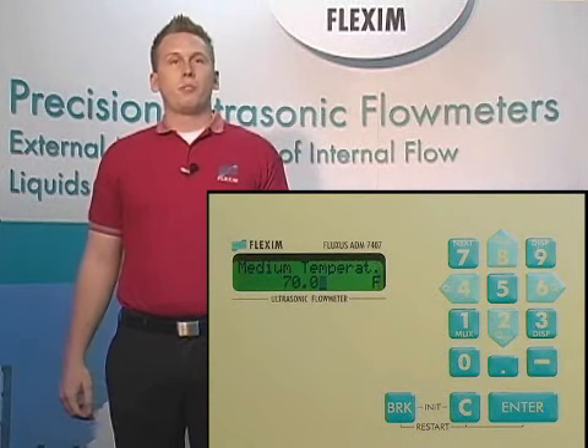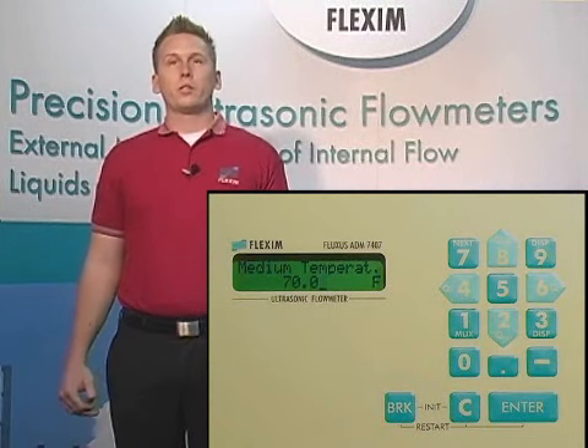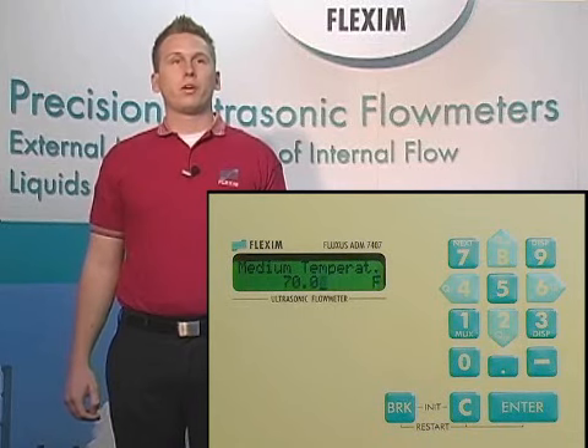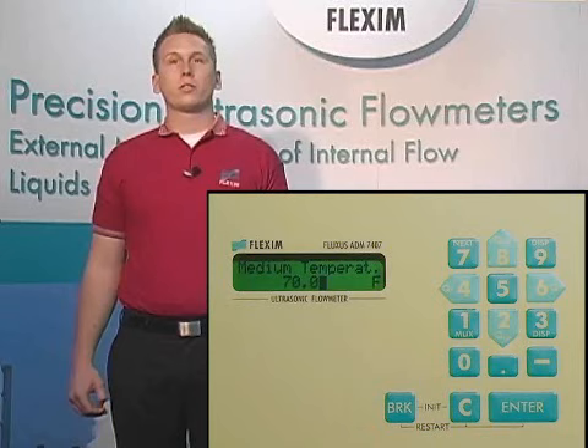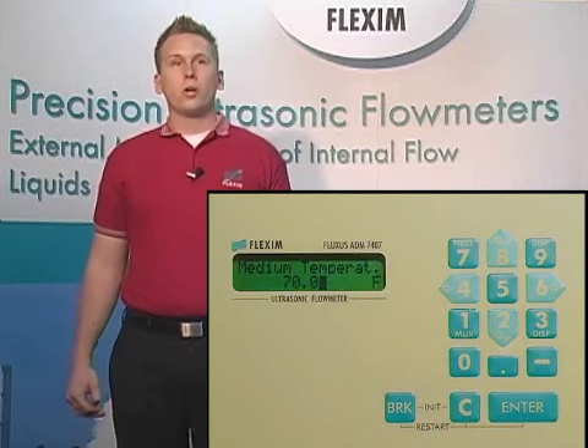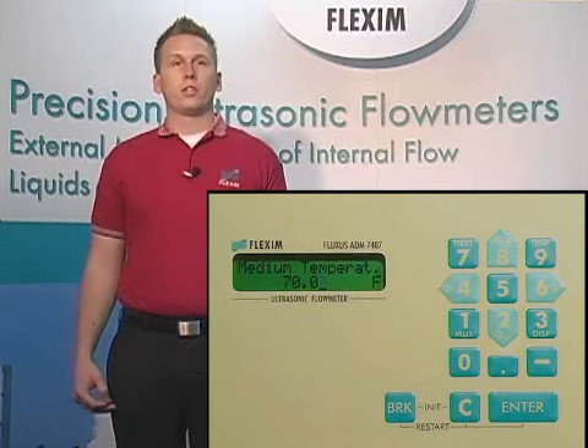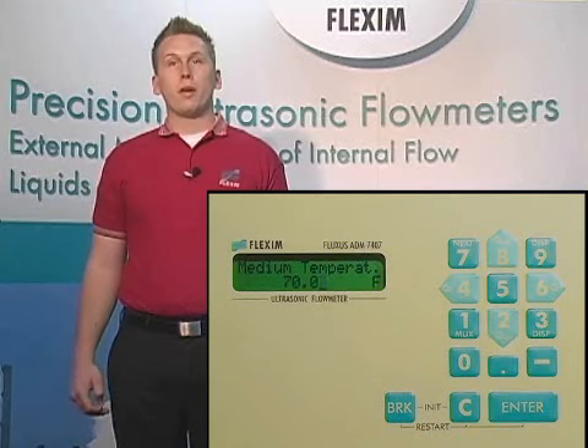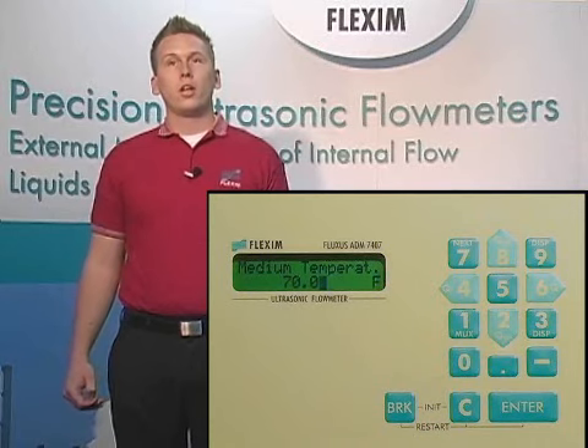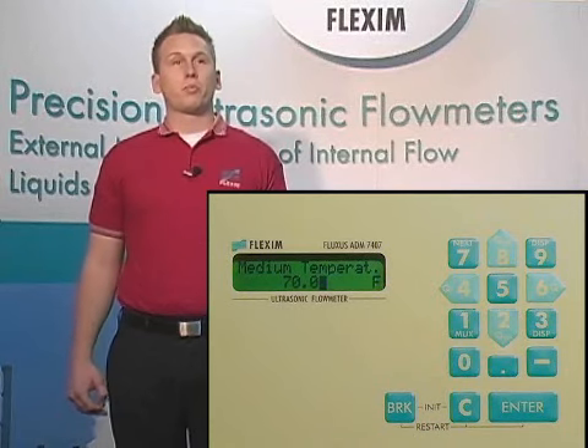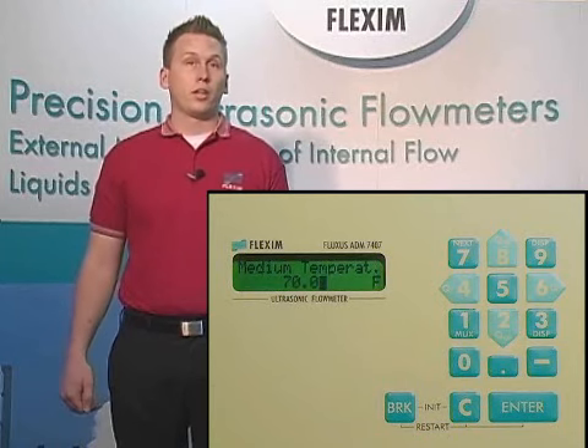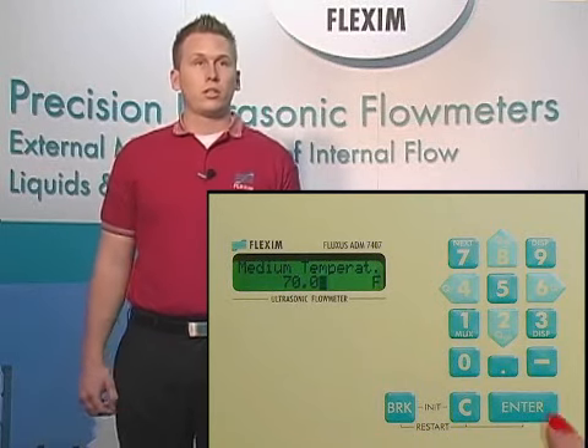Now we're prompted to enter the medium temperature. Here we need to put in an approximate value for the temperature of your fluid. This is only used to help the meter figure out where to tell you to install the transducers. Don't worry if you don't have the exact temperature. You can even put your hand on the pipe and make a guess if you don't know. And this is usually more than sufficient to get a good placement distance for your transducers. Of course, Flexim can measure pipes up to 750 degrees Fahrenheit. Don't put your hand on those.